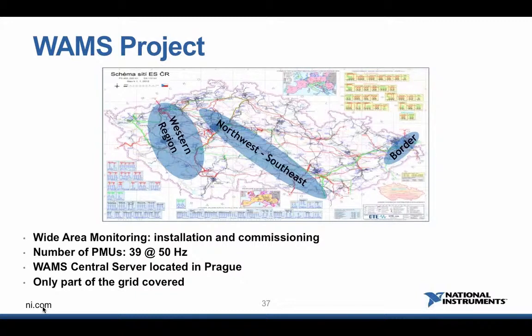It's based on the application of 39 PMUs and the WAMS central server located in the main control room of Czech TSO. The reason for that project was to have a monitoring system helping the operators of the Czech transmission grid see if the grid is in a stable state, and if there is a certain reserve of static power that can be transmitted across the main corridors of 400 kV lines used in the Czech Republic.